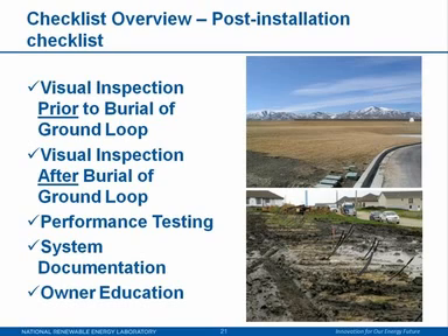Pressure testing the ground loop is a huge issue for these ground source heat pump systems, because that will tell you, once they bury it in the ground, if there are any leaks or cracks in the tube. Are the fused butt joints in the tubing done properly? The pressure test would tell you right away if that was the case, so they need to make sure they do a pressure test on the ground loop.